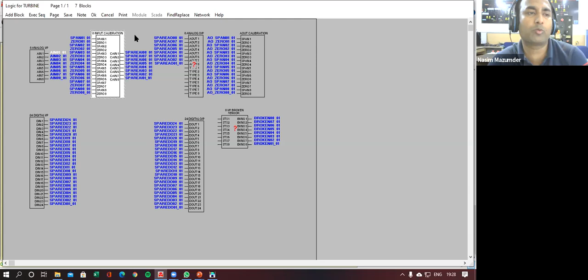The value will be coming to this pin, and at channel number 1 you have to assign the tag of that particular instrument. Suppose I am going to connect a pressure transmitter at this pin. I can give a name to this pressure transmitter, say PI 101_01. So this tag name I have generated; it was not there earlier. I have written PI 101 underscore 01, and in the tag description I can write, say, main steam pressure.